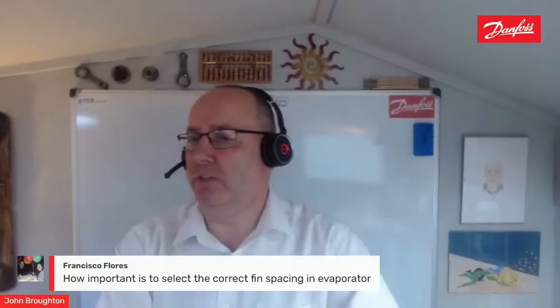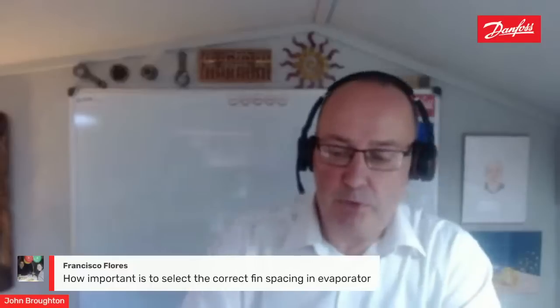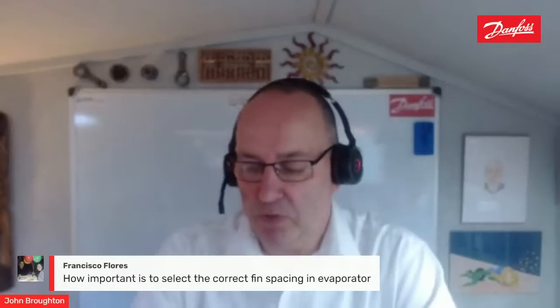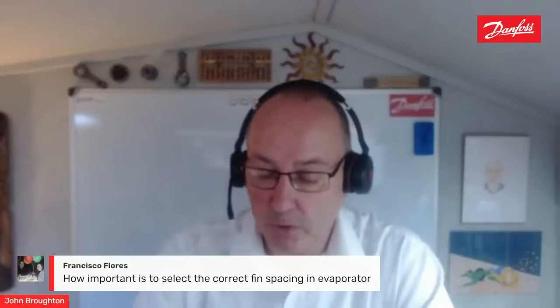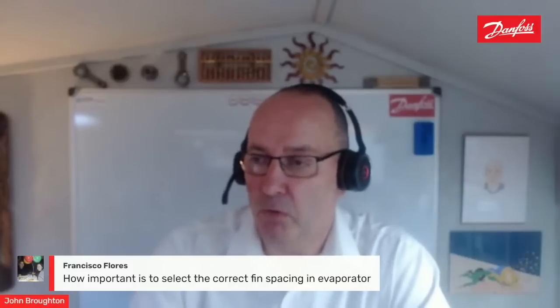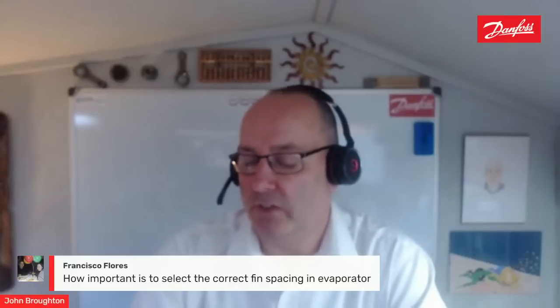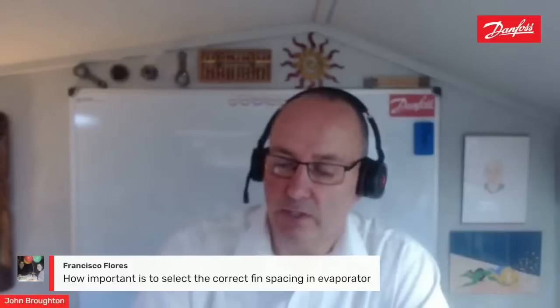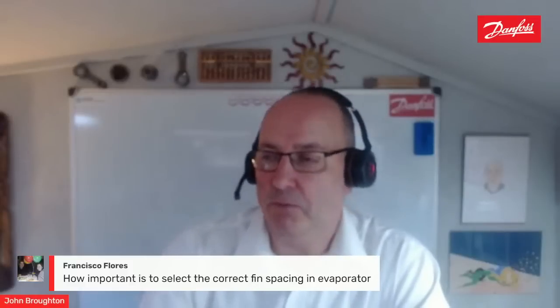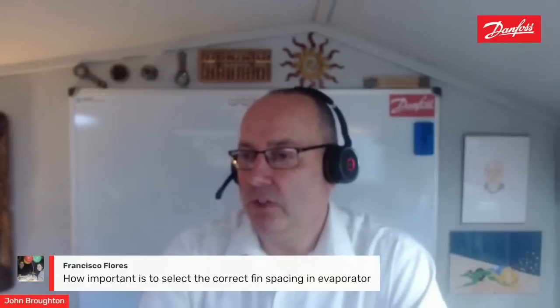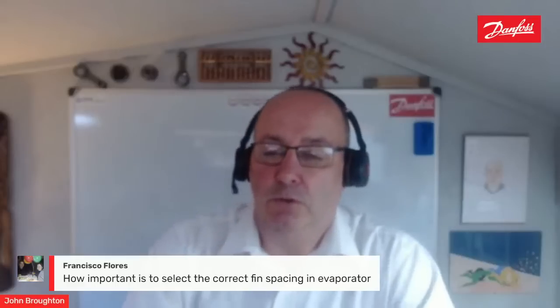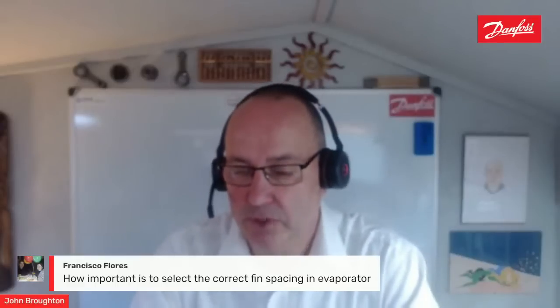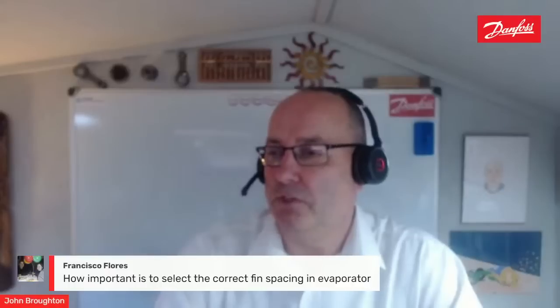Francisco asks from YouTube, how important is it to select the correct fin spacing on an evaporator? It's very important because the colder you go, and also the more moisture that you have in your room, the wider fin spacing that you need. Otherwise, as the frost builds up, that frost will block the airflow across the evaporator and it will not function. Your expansion valve will shut down and you won't get the correct refrigeration effect.